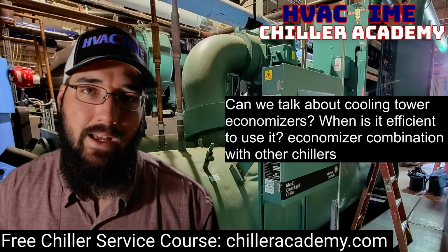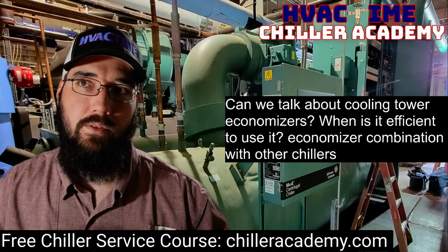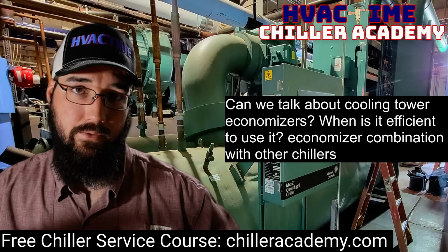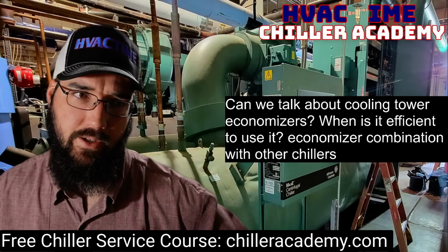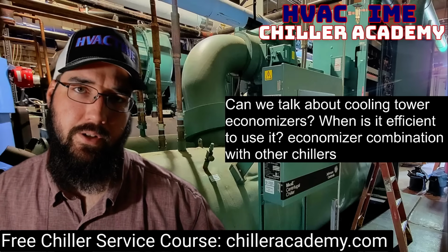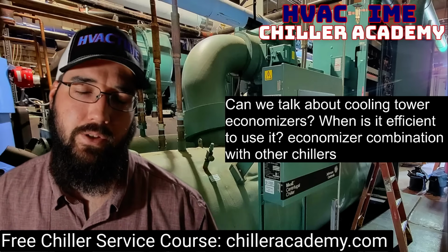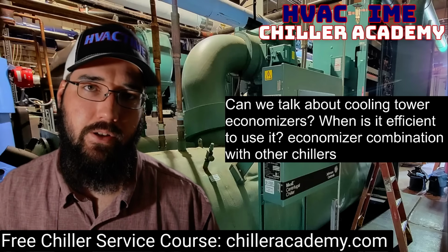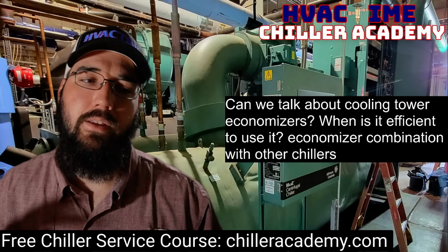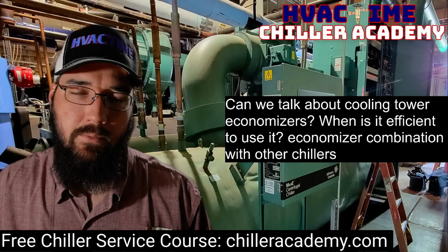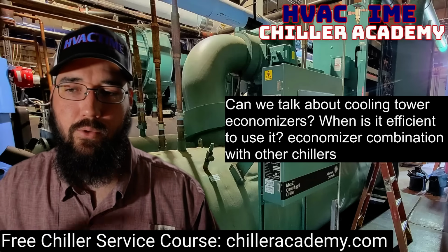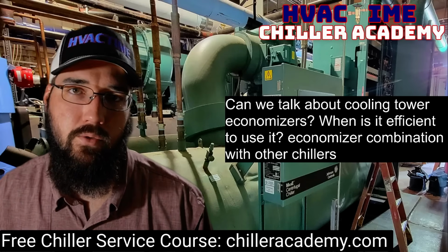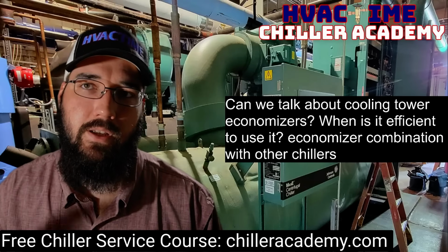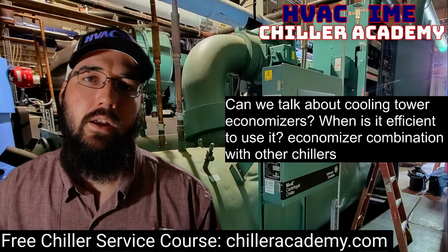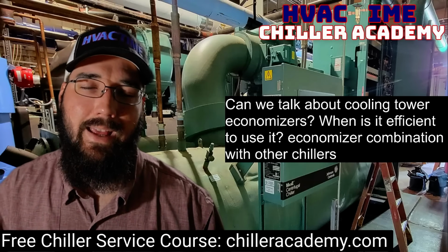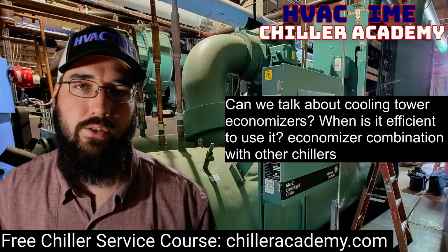So if you don't have that and you're relying on the pressure differentials, well, when you're inverted, you can't feed enough refrigerant into that compressor to keep it cooled, and it will end up overheating on the inverter temperature because of it. You can eventually overcome that, but it's kind of a pain, and you have to go in and do a bunch of manual overrides, especially with the time delays that you should run on those Turbocors. Take the inversion piece of it into account.